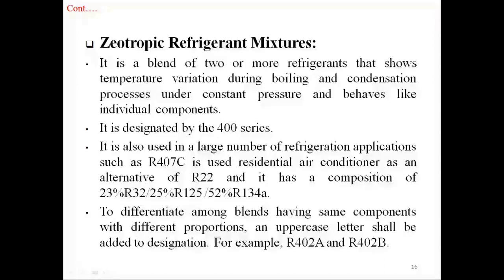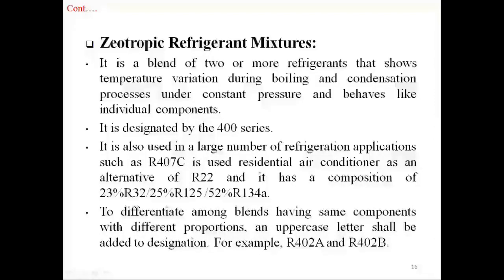Next is zeotropic refrigerant mixtures. It is a blend of two or more refrigerants that shows temperature variation during boiling and condensation processes under constant pressure, and behaves like individual components. It is designated by the 400 series. For example, R407C is used in residential air conditioners as an alternative to R22, and has a composition of 23% R32, 25% R125, and 52% R134A. To differentiate among blends having the same components with different proportions, an uppercase letter is added to the designation — for example, R402A and R402B.